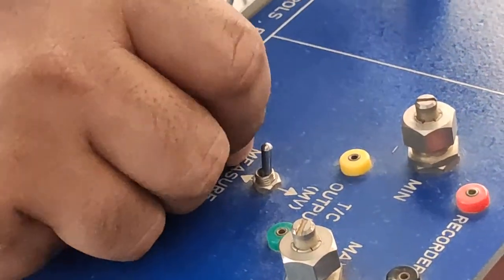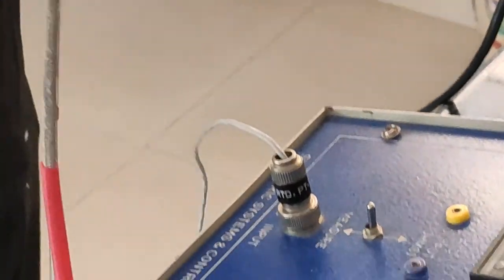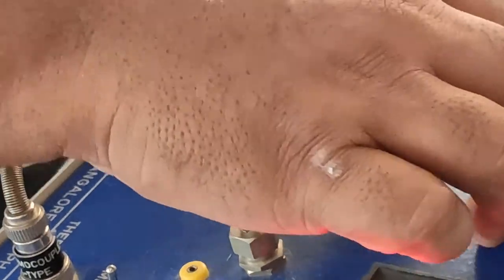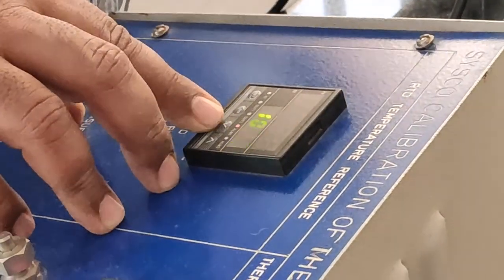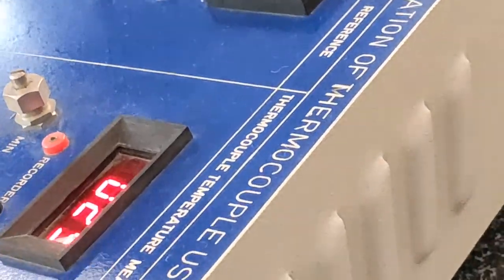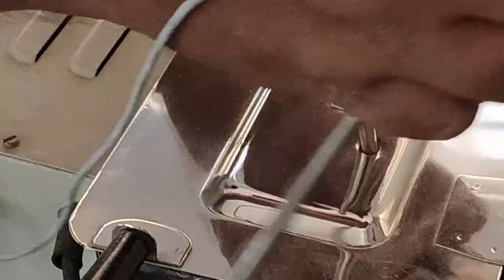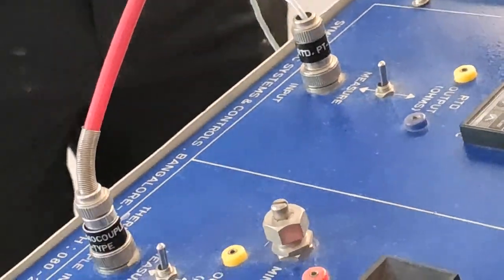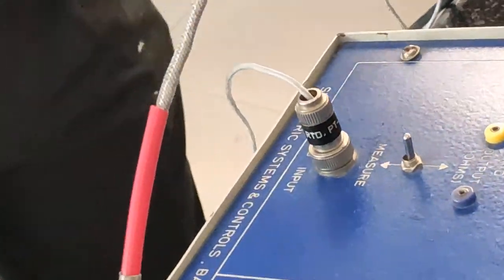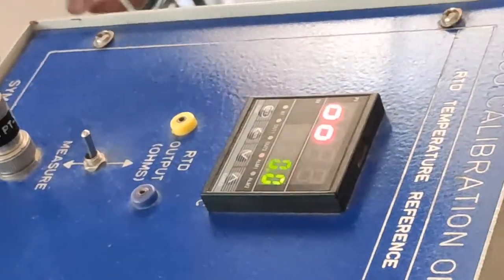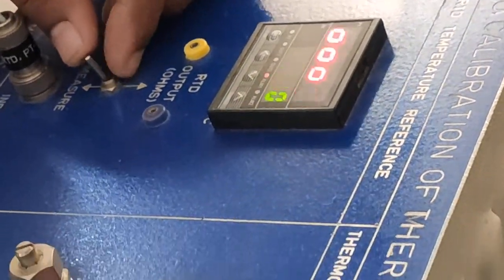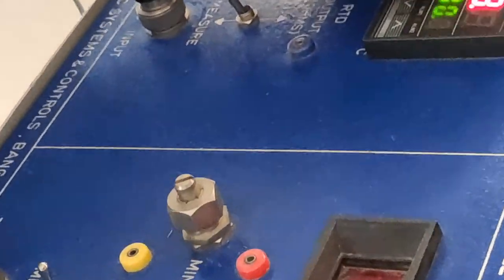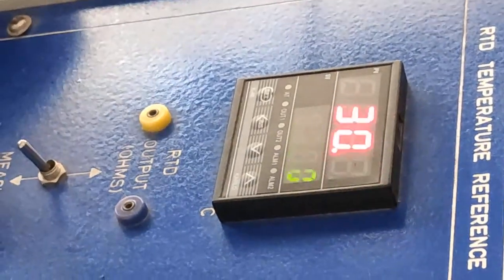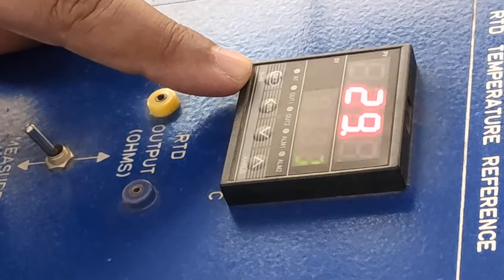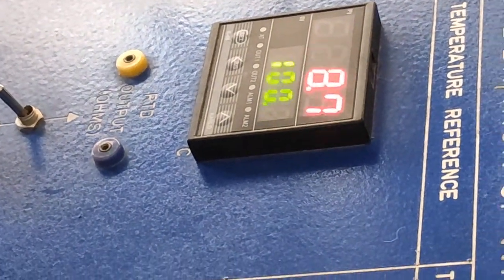The min and max show the minimum and maximum temperature. It is set back to the room temperature, and you can set the temperature using this temperature measuring device. Now insert these thermocouples inside the water bath. Normally we have an arrangement for stirring, but we don't have any provision for that right now. I am going to increase the thermostat temperature, and the heater is on. Now we can see there is some rise in temperature. This is the indicator for the RTD, and this is the thermocouple which is fixed as a J-type over here.